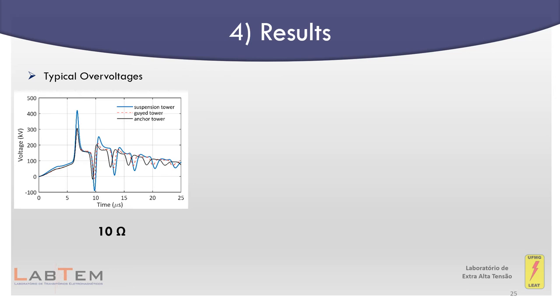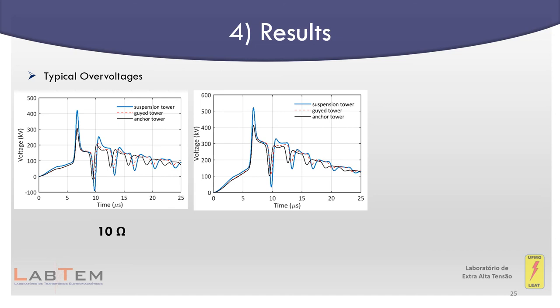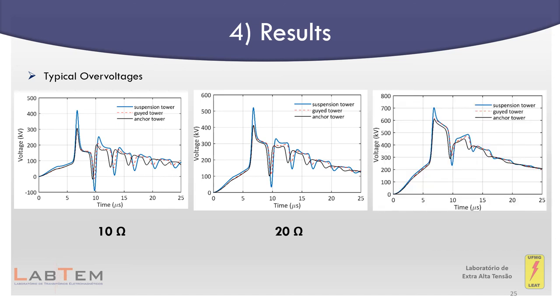The figures show the overvoltages arising across the lower left insulator string due to a direct strike to the tower top, considering the three distinct typical towers of the 230 kV line and assuming tower foot impedance values of 10, 20, and 40 ohms. The suspension towers present the higher peak overvoltage values in comparison with both guyed and anchor towers, which in turn show similar peak values. This stems from the higher equivalent surge impedance of the suspension towers. The differences between the voltage curves tend to decrease with increasing tower foot impedance.